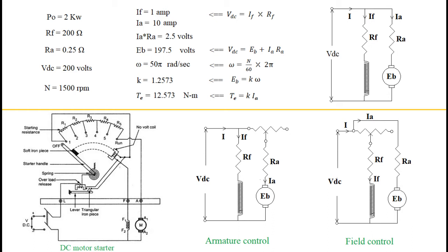Consider the starter circuit diagram shown on screen. The motor needs to be started by inserting 5 resistors in the armature circuit, which are removed one by one. For example, assuming 50 ohms of resistance from the 5 resistors, and since armature resistance of 0.25 is negligibly small, the armature circuit will carry approximately 4 amperes initially.